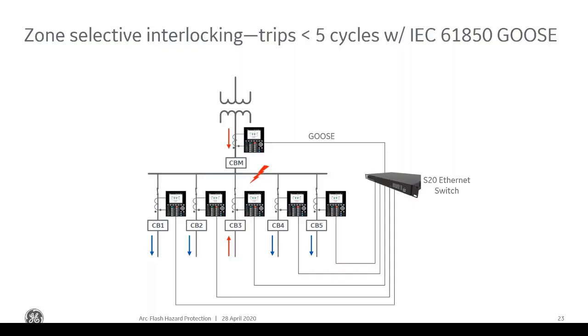So in order to deal with a lot of these so-called issues with overcurrent bus protection, we generally increase the sensitivity and add some time delay. If you have an external fault and your CT starts to saturate, you want to give the CT enough time to recover. Or if you have a fault with a lot of harmonics on it initially, you can cause different mismatch in the CTs when you strike the fault. So you want to give that overcurrent some time to settle down so it doesn't misoperate.